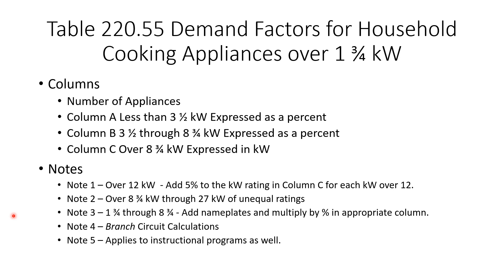The table has four columns. The first is the number of appliances. Column A covers appliances that are over one and three-quarters and less than three and a half kilowatts, expressed as a percent. This is important because not all columns are expressed as a percent, which can make it very confusing.